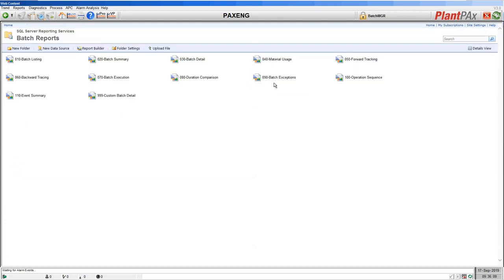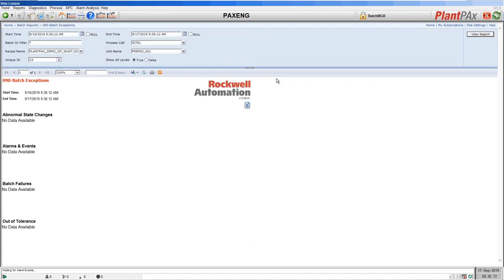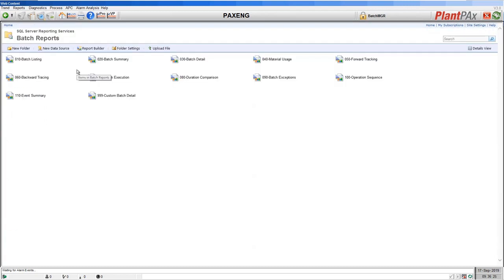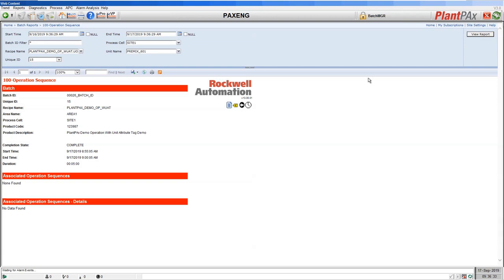The next report is a duration comparison report, which is all about comparing executions one batch to another. In the last 24 hours we've run two batches, and the second batch took longer than the first. You can then go and look at the details of that batch to see where the time was used. The batch exceptions report purely shows issues that occurred on a batch — when we ran our batch we didn't have any issues, so there's no data available. The next report is the operation sequence. If you use sequence manager technology in Logix, you can connect FactoryTalk Batch to run those sequence manager sequences and this report will show any of those sequences that ran in your recipe. In this demo we didn't do that, so our report has none shown.